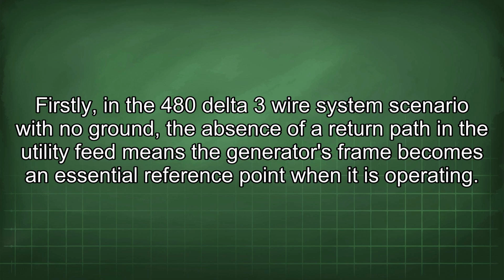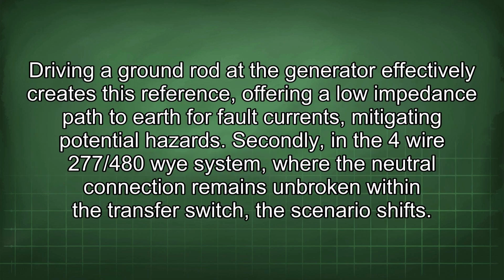Firstly, in the 480 delta 3-wire system scenario with no ground, the absence of a return path in the utility feed means the generator's frame becomes an essential reference point when it is operating. Driving a ground rod at the generator effectively creates this reference, offering a low impedance path to earth for fault currents, mitigating potential hazards.